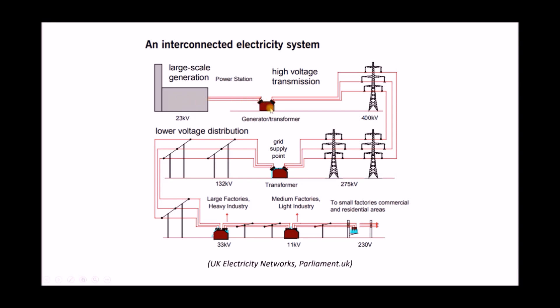As we move from left to right we need to step up that voltage — from 23 kilovolts all the way up to 400 kilovolts. There's a very important reason for that. Once electricity has been generated it needs to be transmitted over the transmission network, which runs the entire length of the country. The idea behind stepping up the voltage is that by stepping up voltage we step down the current, so the electricity being transmitted has a much lower current and is less likely to incur energy losses.